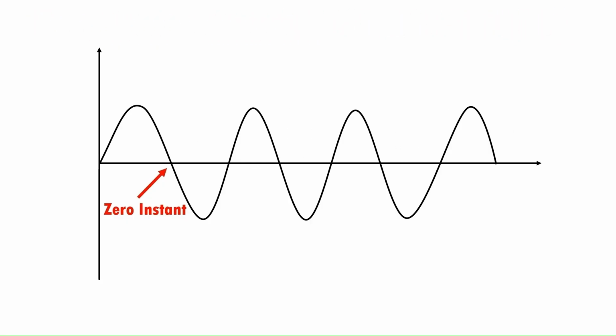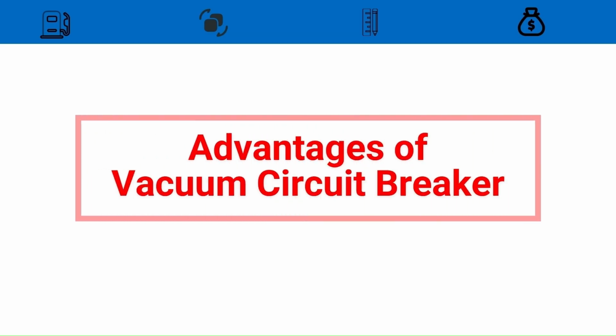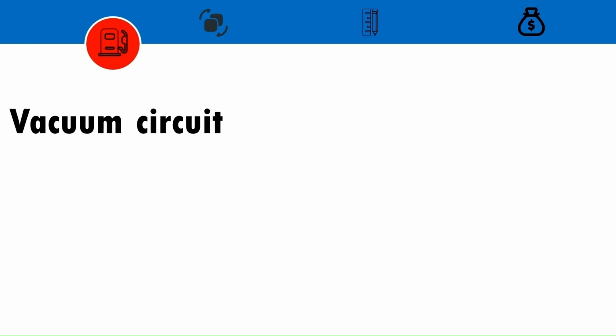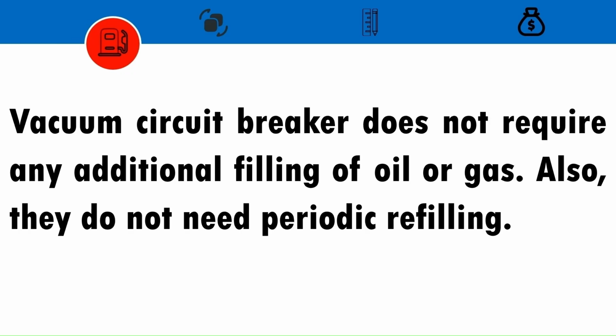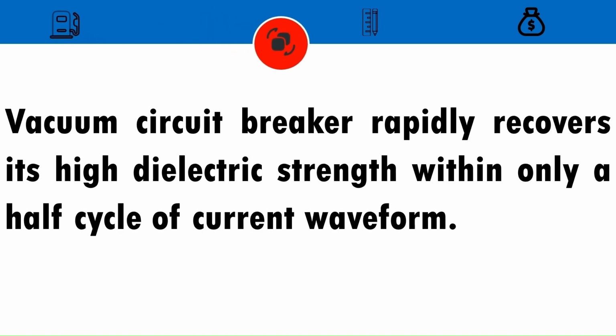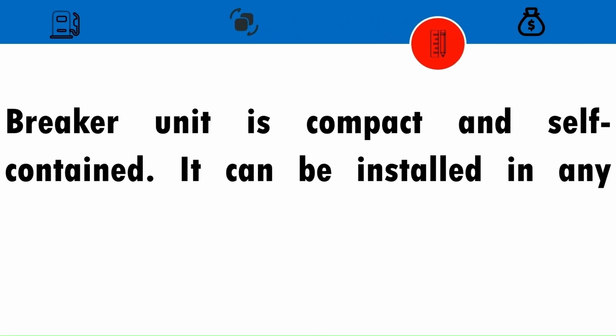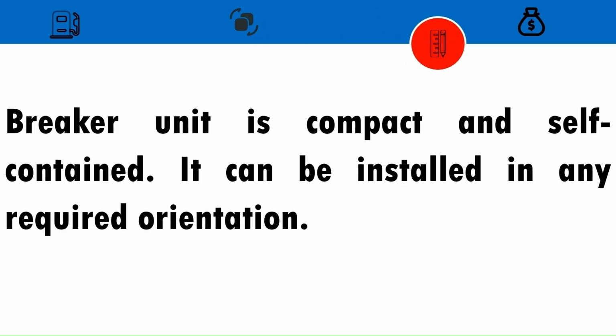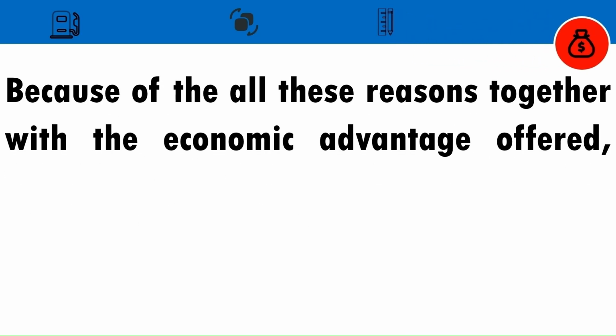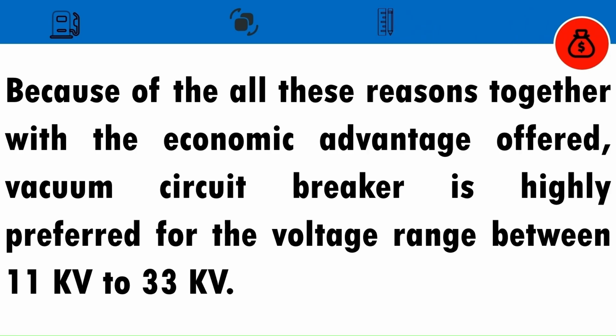Now, we discuss advantages of vacuum circuit breaker. Vacuum circuit breaker does not require any additional filling of oil or gas. Also, they do not need periodic refilling. Vacuum circuit breaker rapidly recovers its high dielectric strength, which is within only a half cycle of current waveform. Breaker unit is compact and self-contained. It can be installed at any required orientation. Because of all these reasons together, with the economic advantage offered, vacuum circuit breaker is highly preferred for the voltage between 11 kV to 33 kV.